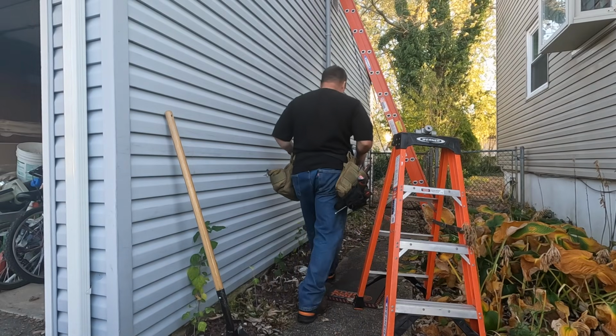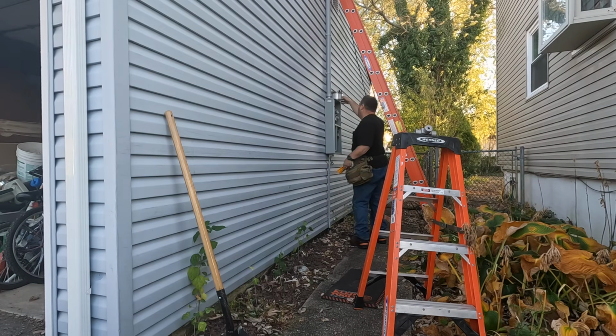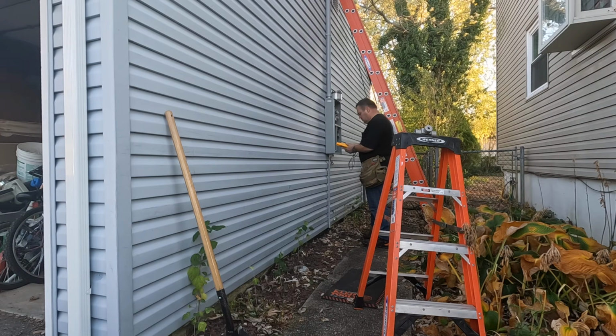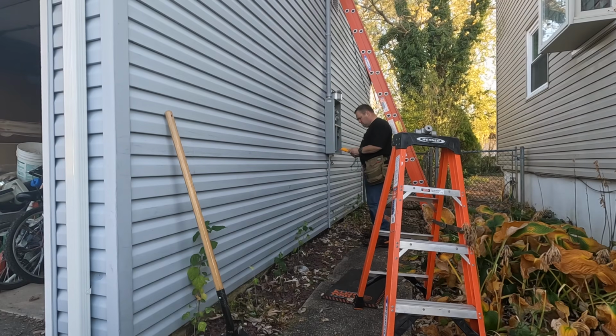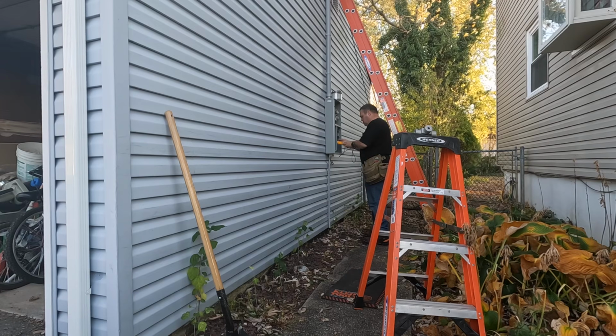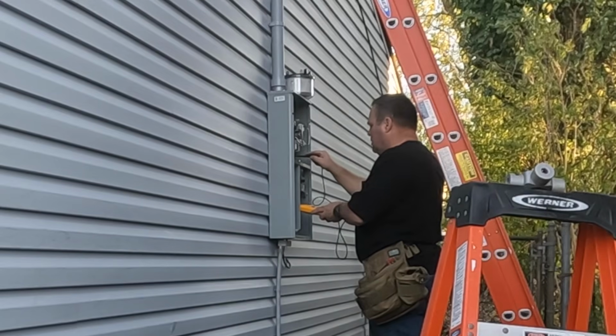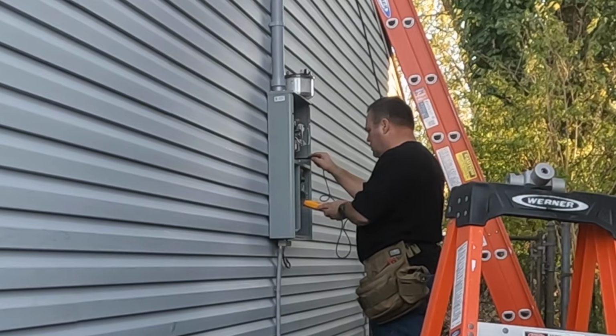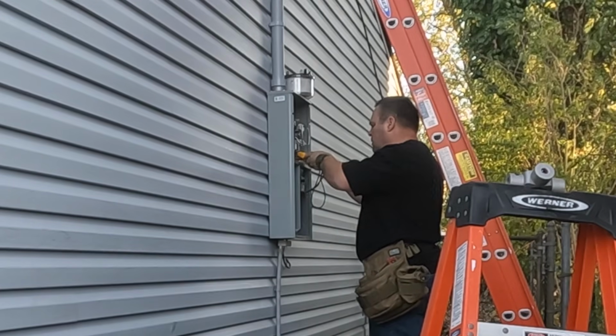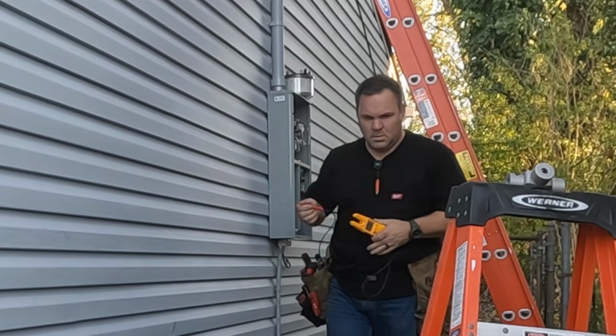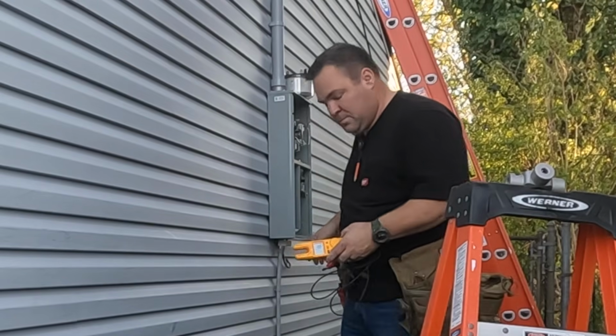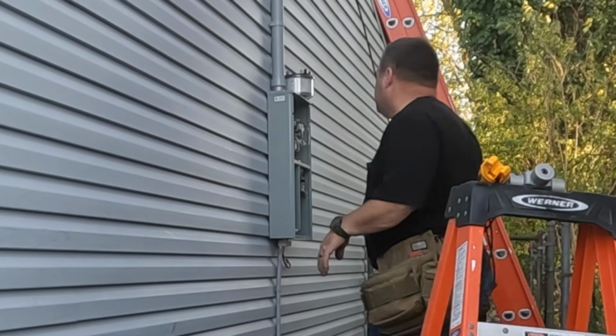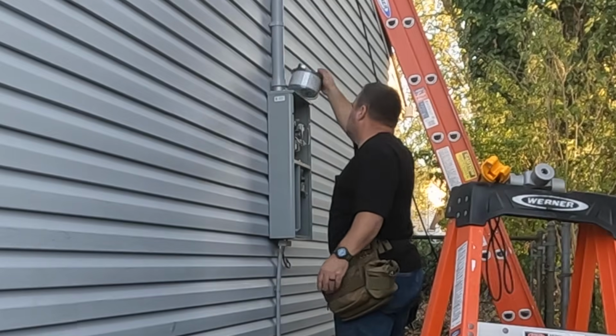So once I do connect it, before I put the meter in, I'm just going to take my Fluke T6 tester here and check on the line side to make sure there's 240 volts between the legs. And then of course I'll also do a continuity test on my load side to make sure I didn't make any errors. Once I get the all clear, I'm able to put the meter back in, turn the main breaker on, and start turning on the rest of the circuits to the house.